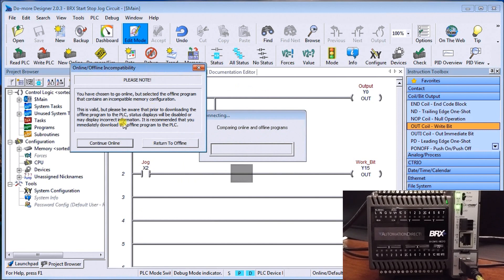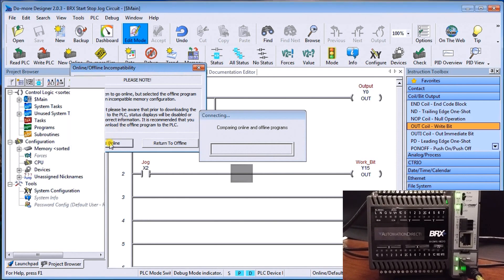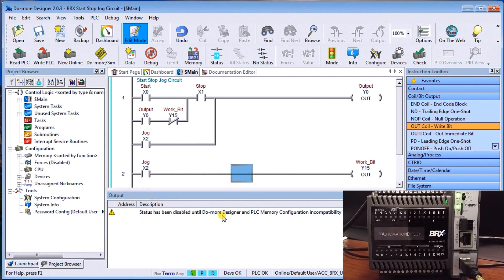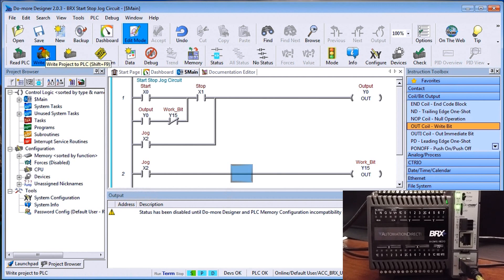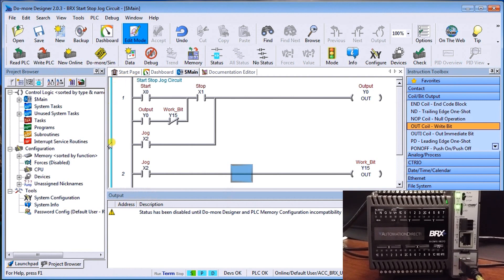And then our incompatibility mode, it now says, look, we're going to go online, offline compatibility. So what it will do is it will still connect online, but it won't do everything. And we'll show that in a second here. So we'll continue online. My output down here says status has been disabled until do more designer and PLC memory configuration incompatibility is resolved. Now, in order to resolve that incompatibility, we actually have to write the information from the project into the PLC along with all the configuration, et cetera, that comes with it. So if I look here up on my ladder, you'll notice that we now have a blue line here indicating that what's in our disk memory is not in our PLC memory.